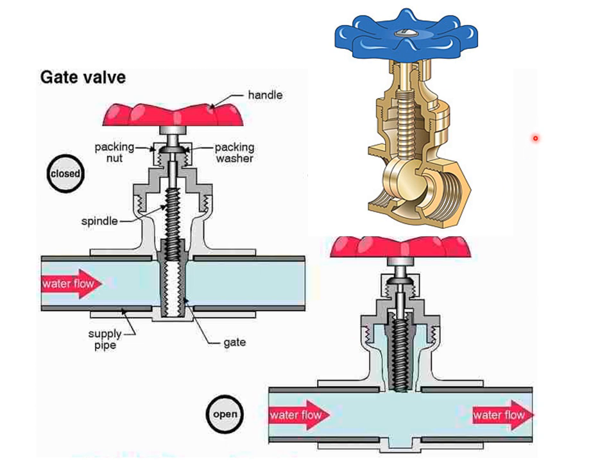This is the configuration of a gate valve. The ball valve is very handy and easy to use because by just turning a quarter radius we can put the water supply on or off. However, in the case of a gate valve or sluice valve, the internal configuration shows disks which block the path of water when at a certain position. By turning the handle multiple times, the disk can be moved up or down and water supply can be restored or stopped. Ball valves usually don't have a very long life and start creating problems; however, the gate valve has a very good life. The only disadvantage is that we have to turn it multiple times in order to keep the water supply on or off.